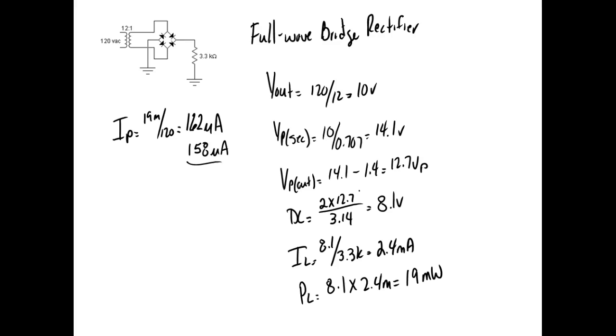And then what size fuse I would use, I would multiply that times 3, which would be 300%. And then I would round it down to the next standard value.